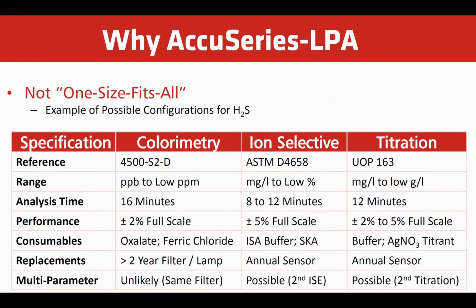Analysis time, if this is important and it meets the criteria where we could use ion selective, obviously you can see it's quicker, or titration. And if we can do them as opposed to colorimetric, we would offer this if that's important. Performance, colorimetric or titration obviously gives you your best repeatability and performance compared to ion selective electrode, as that's 5% of full scale compared to 2% with colorimetric, or depending on the titration, 2% to 5% on that.